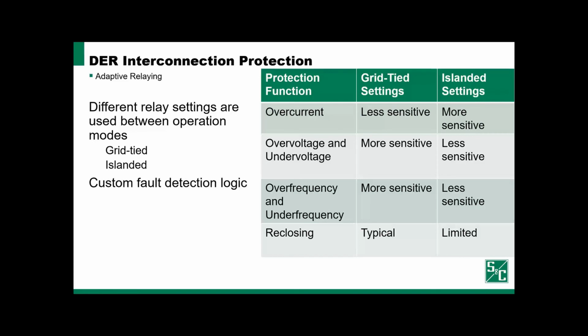Now, how can we change the settings? What kind of things are we looking to change? One of them is overcurrent. When we're grid tied, we can have less sensitive settings to detect the high fault current. While we're islanded, we may want to make it more aggressive and more sensitive. You might ask, why not just make it more sensitive all the time? Well, when we're grid tied, we could have transformer magnetizing inrush or large block loads or other conditions that could cause the current to elevate, and we don't want to cause nuisance tripping or nuisance operations. Over under voltage and over under frequency are also settings that often change between grid tied and islanded modes. When we're grid tied, the system is stiffer and those settings can be more sensitive. When we're islanded, those settings must be a little looser to allow for system dynamics when we're accepting load, and typically are less sensitive, allowing a little bit more normal variation.